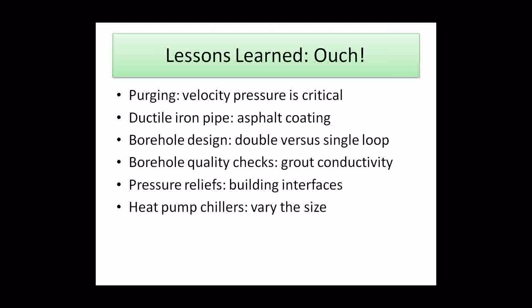And those lessons learned are more in the constructability of the project, and that's purging. Once all your piping's installed in the ground, we found that you really have to get your velocity pressure up to push anything that got into the piping system out of the piping system. That includes rocks and so forth. Ductile iron pipe, we had an asphalt coating specification. That's been taken out of our spec.